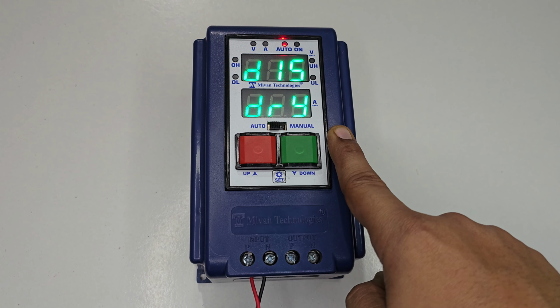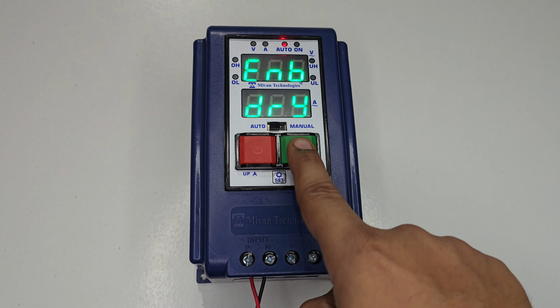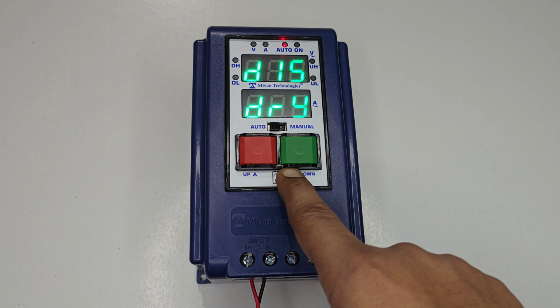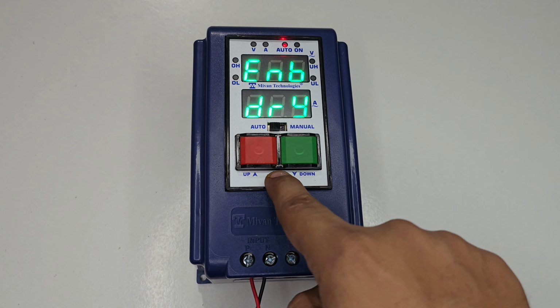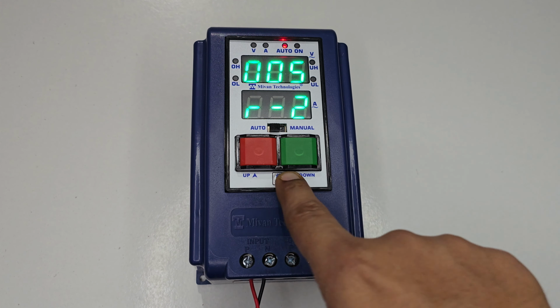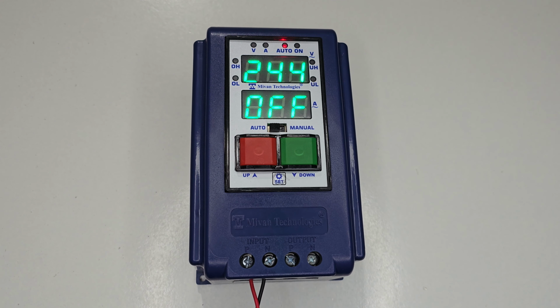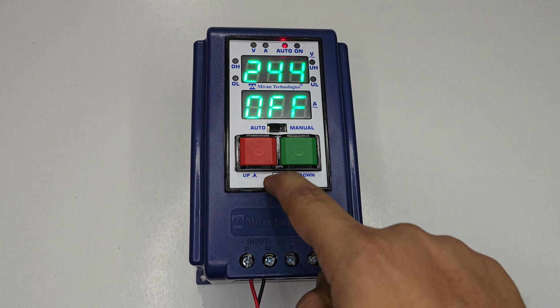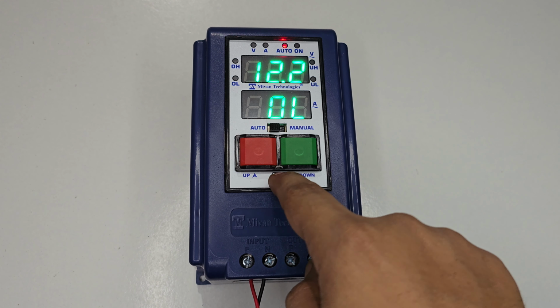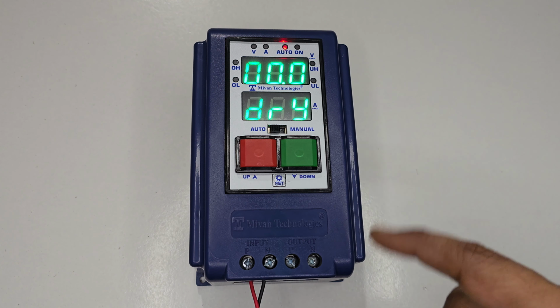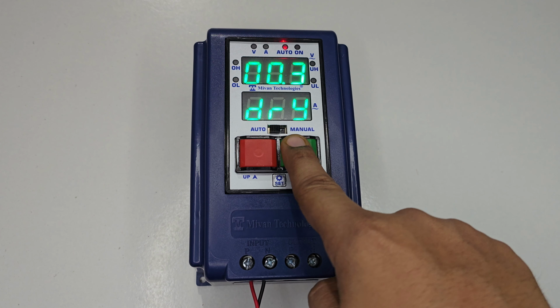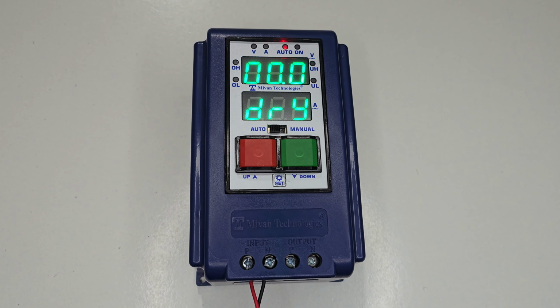Here you can see a dry enable disable option. By pressing the up and down key, you can enable and disable the dry running option. Make it enable and press the set button until it comes to the main menu. Now in the main menu, press the set button, the overload value will come. Press the set button, the dry current option comes. Here you can adjust the dry running current by the up and down key. Adjust the dry run current according to your motor and press the set button to store the value. Generally the dry run current value will be 25% lower than the load value.